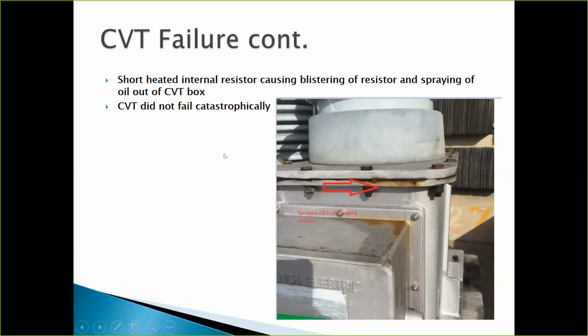The key point here is the CVT did not fail catastrophically, and I ought to mention to you that the thing was in alarm for about 2 weeks before the techs ever got out there to it. So I believe that we could have even prevented this from happening had we responded sooner. It's kind of an out-of-the-way location. It wasn't a very close location, and they didn't see it as a high priority. But that was a lesson learned for us that when these things alarm, we need to respond a little quicker. But I'm calling this a success because it wasn't a failure. It wasn't a catastrophic event. It didn't operate the system. We caught it before any real damage was done.